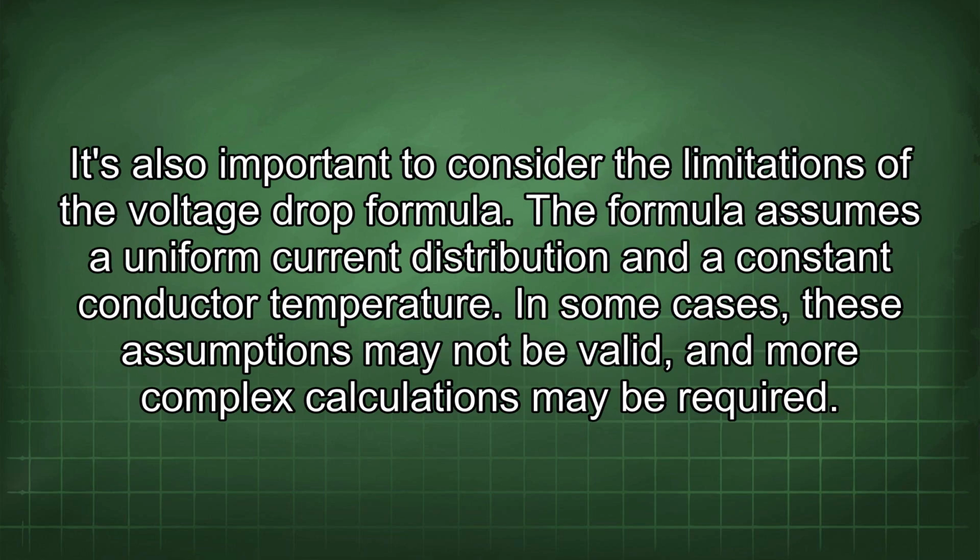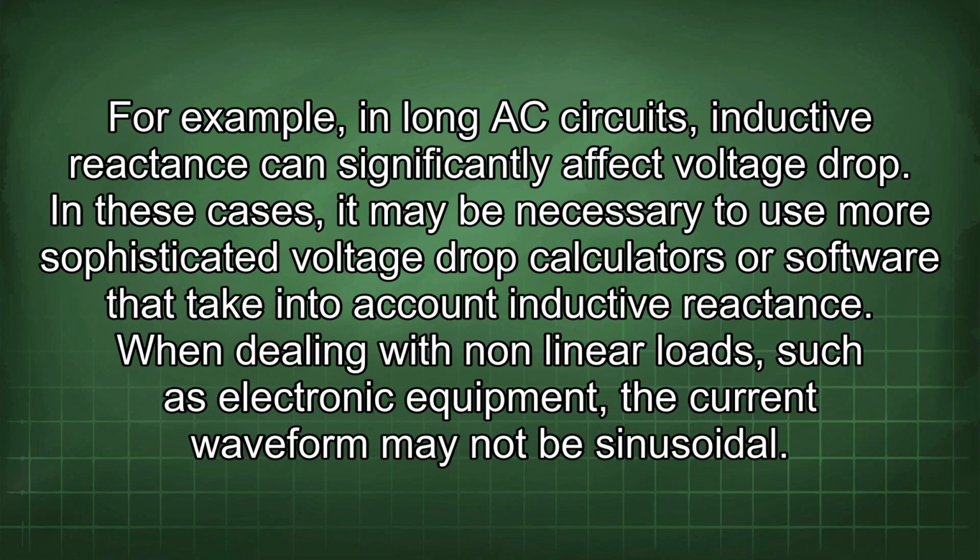It's also important to consider the limitations of the voltage drop formula. The formula assumes a uniform current distribution and a constant conductor temperature. In some cases, these assumptions may not be valid, and more complex calculations may be required. For example, in long AC circuits, inductive reactance can significantly affect voltage drop.